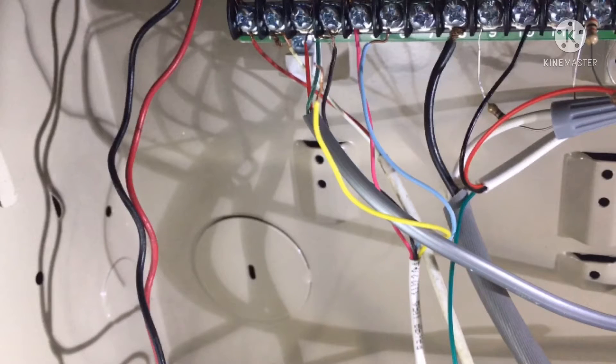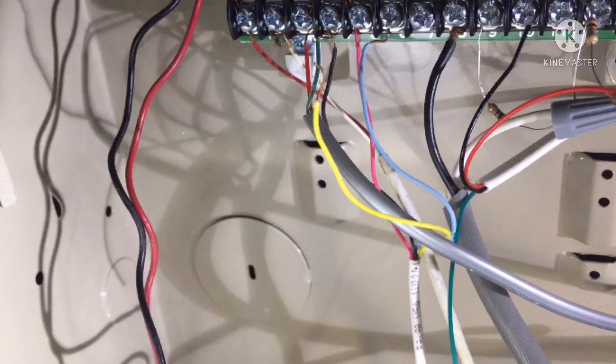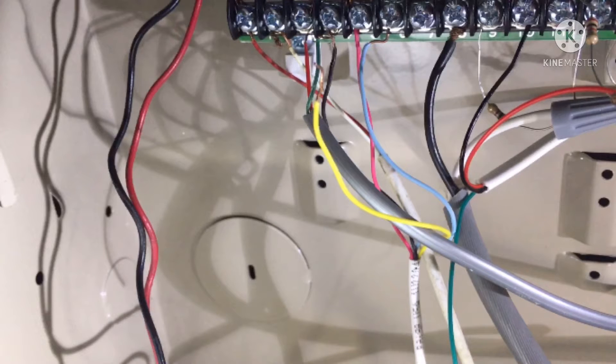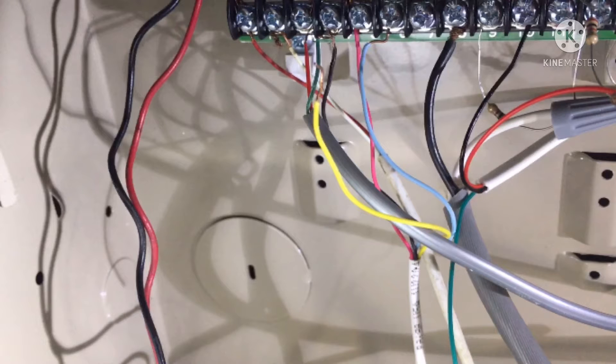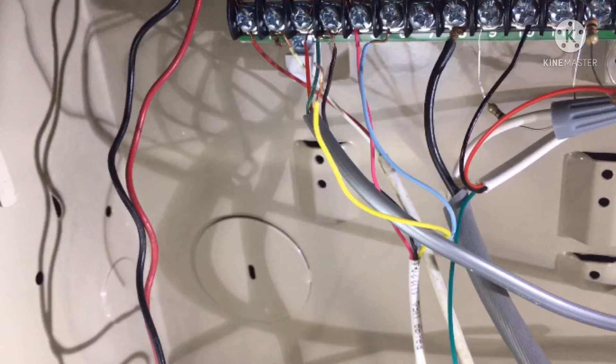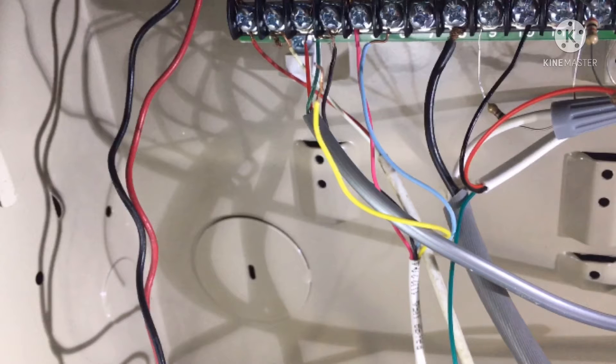If so, that means that the keypad is not getting any data from the panel. If you don't have the cables undone and they're tightly in the terminal, that means that something has shorted out in the wall, either cut or broken. Let's fix that.